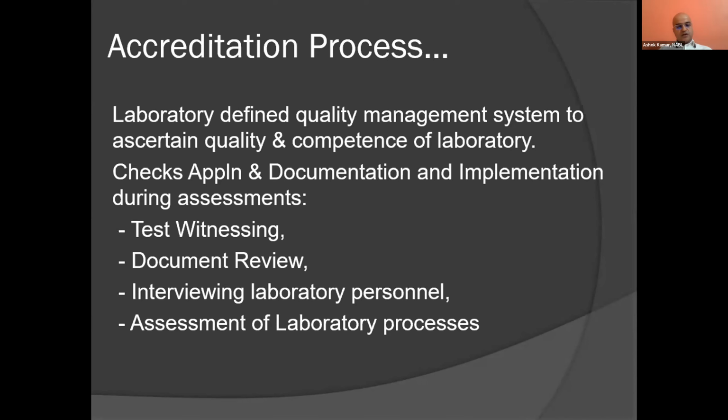Laboratory persons' competence is checked with test witnessing, interviewing the laboratory personnel, and the assessment of laboratory processes. This gives confidence to the accreditation body that the lab is following the processes as defined by the laboratory in their quality management system, which is finally as per the ISO 15189 standard.